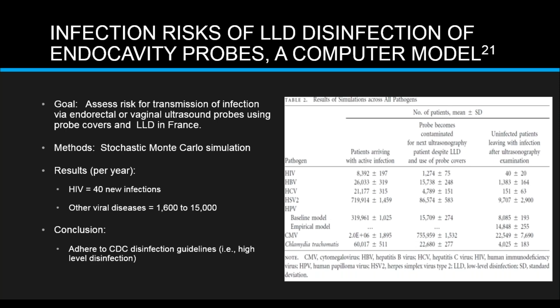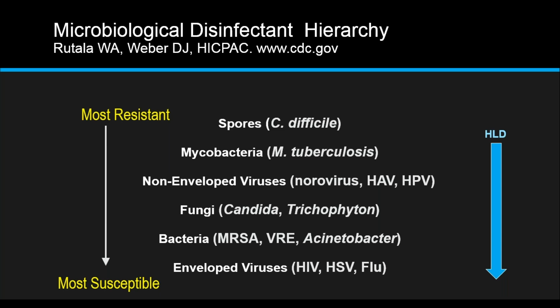The conclusion is to adhere to guidelines such as those by the U.S. Centers for Disease Control and many other groups that we'll talk about to properly clean and then high-level disinfect all endocavity probes. Now, one of the reasons for using high-level disinfection is shown on this slide. That is, high-level disinfection will inactivate all microbes with the exception of high numbers of spores. A few spores may remain, but it will kill mycobacteria, importantly non-enveloped viruses such as norovirus, HPV, fungi, bacteria such as MRSA, Acinetobacter, enteric organisms such as E. coli that would be in the vagina or in the rectum, and of course enveloped viruses. Low-level disinfection will not reliably inactivate mycobacteria or viruses.